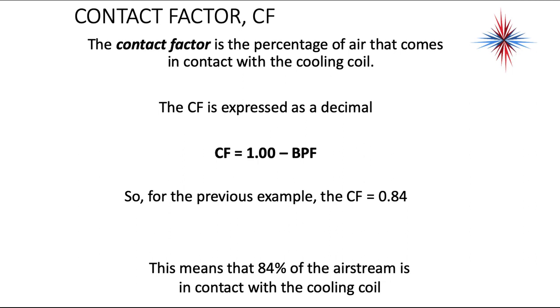The contact factor is the percentage of air that comes in contact with the cooling coil — basically the opposite of the bypass factor, also expressed as a decimal. To get the contact factor, you take 1.00 minus the bypass factor. In this example, we had a bypass factor of 0.16, so 1.0 minus 0.16 gives us a contact factor of 0.84. That means 84% of the airstream is actually coming in contact with the cooling coil.